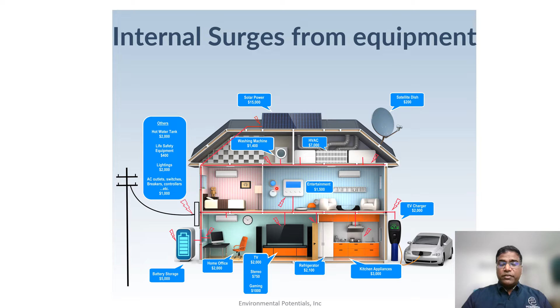So now what are the consequences of this electrical noise? There are many power quality issues that are caused by the surge and the noise. I would separate them into three categories. One is protection related issues, which can cause damage to the system by the surges, high voltage peaks and transients. And the second one is performance related issues, which decrease the load's performance when they're hit by electrical noise. For example, people call it a ghost in the system, right? They just shut off the electrical conveyor belt because they don't know what's going on and they have a sporadic issue. They have to reset the breaker, they have to reset the motor, they have to reset the whole system again. So it decreases the performance. So that is the second issue.